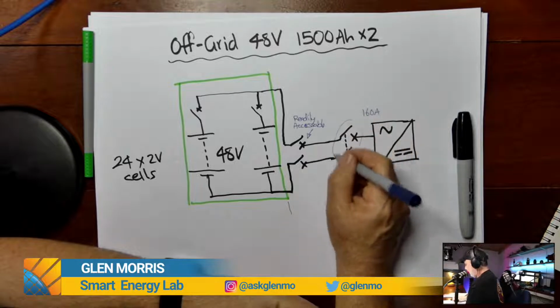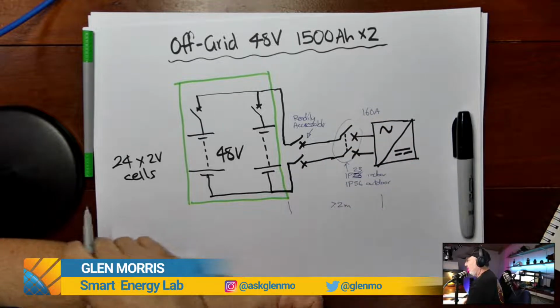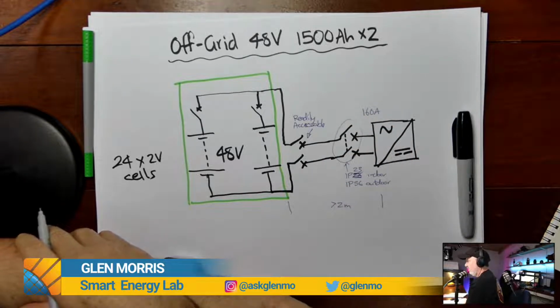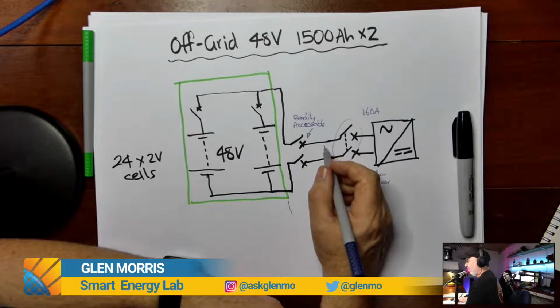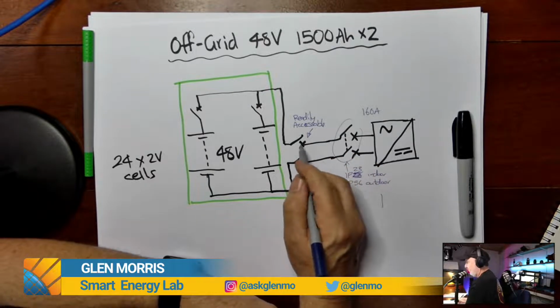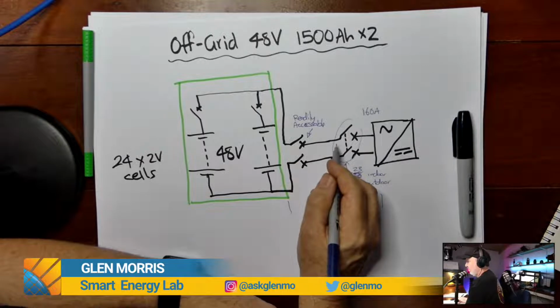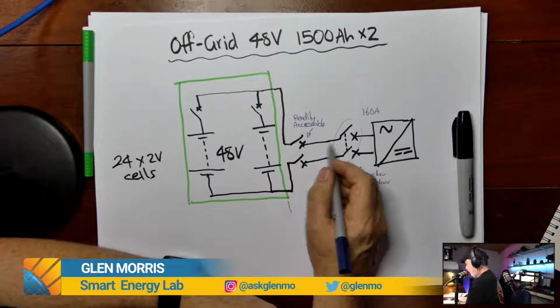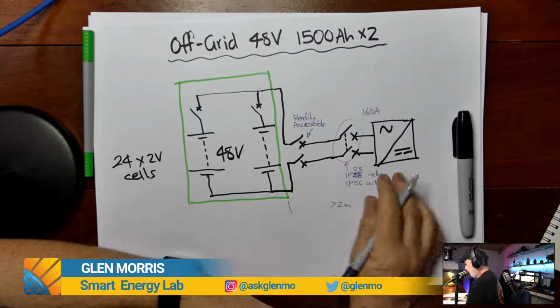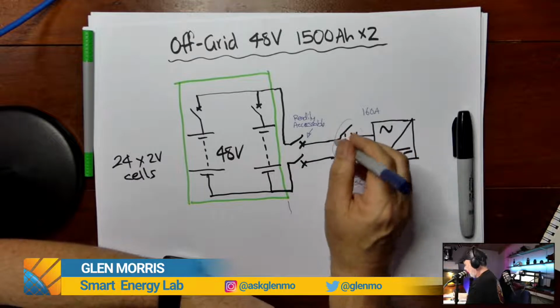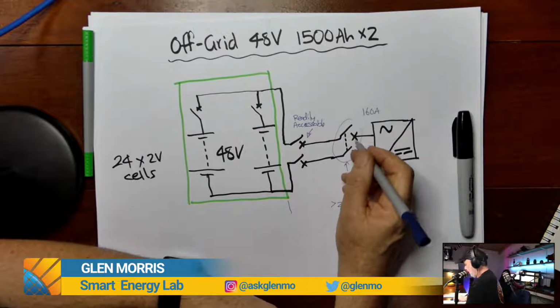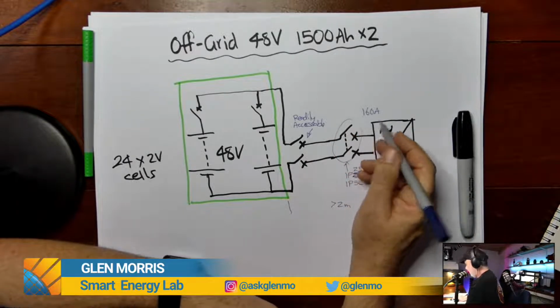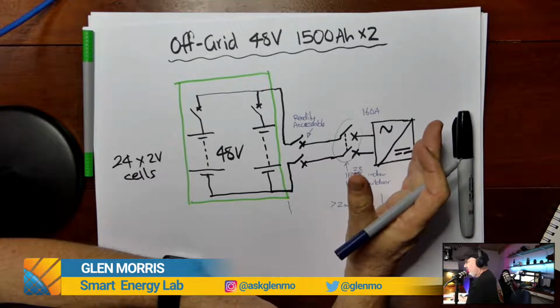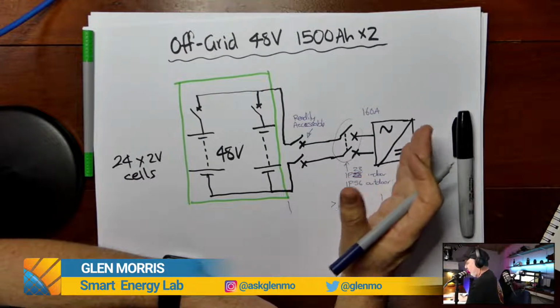So our protection here and the size of our cables needs to be suitable for the load. So the cables must be able to carry the current, and the protection must protect the cables in case of a short circuit as well. So the sizing of these will be determined by both the load and the protection. So it's just the same theory as you would use in any AC design, but it's DC.